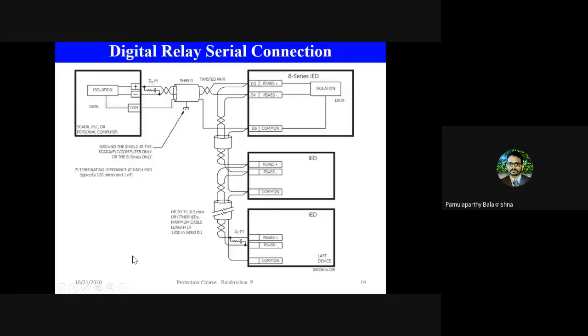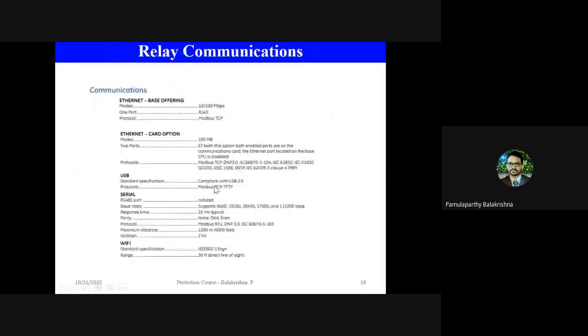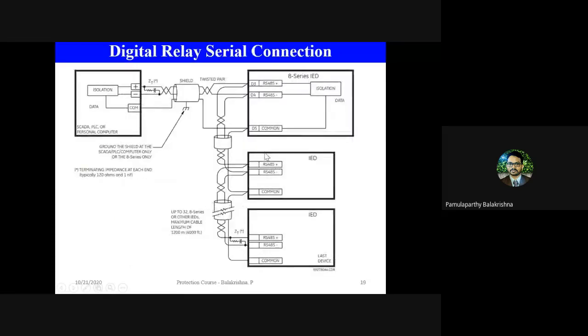As I told, serial communications are used when there is no option of Ethernet. These serial communications are connected in a daisy chain fashion. What does daisy chain mean? You have a master station that wants to communicate with various IEDs. A cable is laid in a serial manner, first from this device to the first IED, the first relay. Then from this relay the cable goes to the second relay, and from that relay the cable goes to the third relay. Like that, they are connected in a daisy chain fashion. So at any point of time, if this device wants to communicate with that device, the message has to go like this.